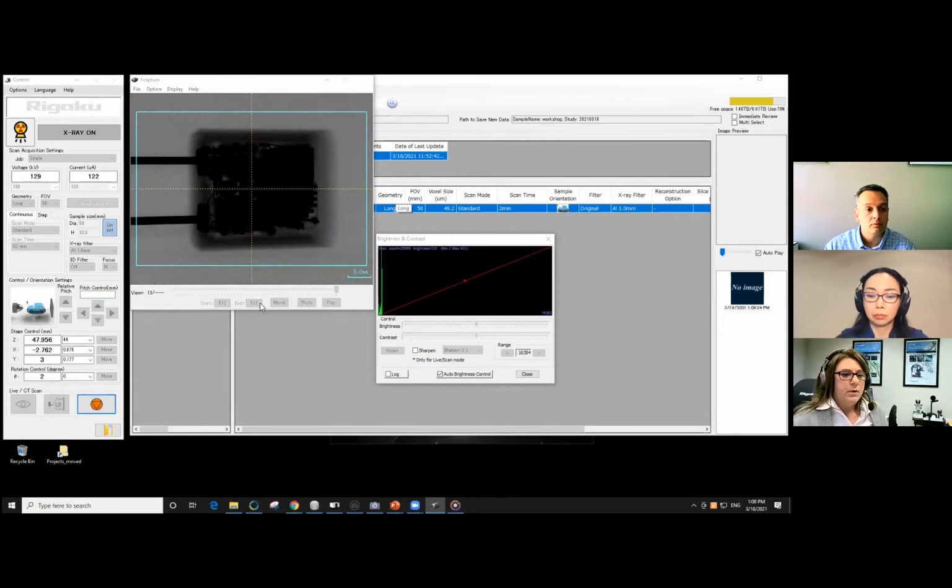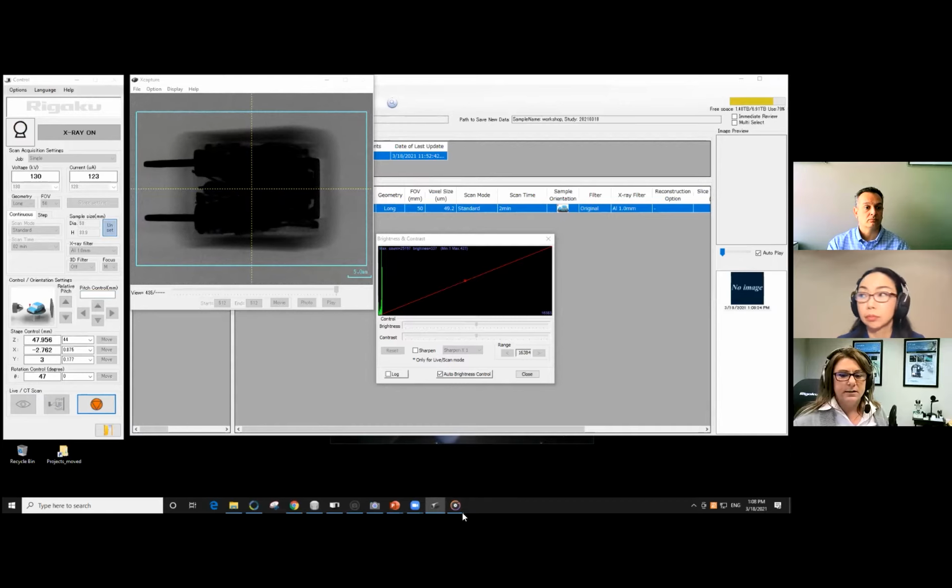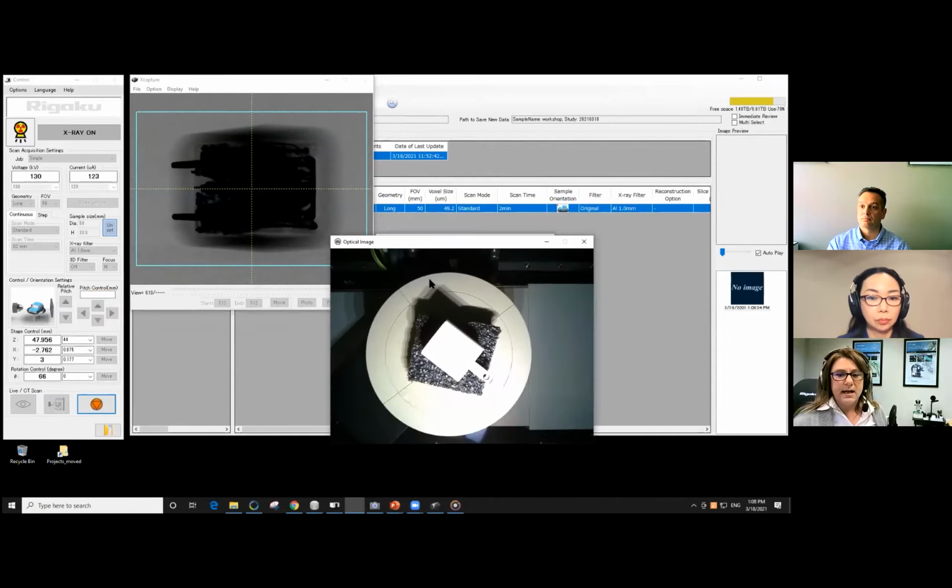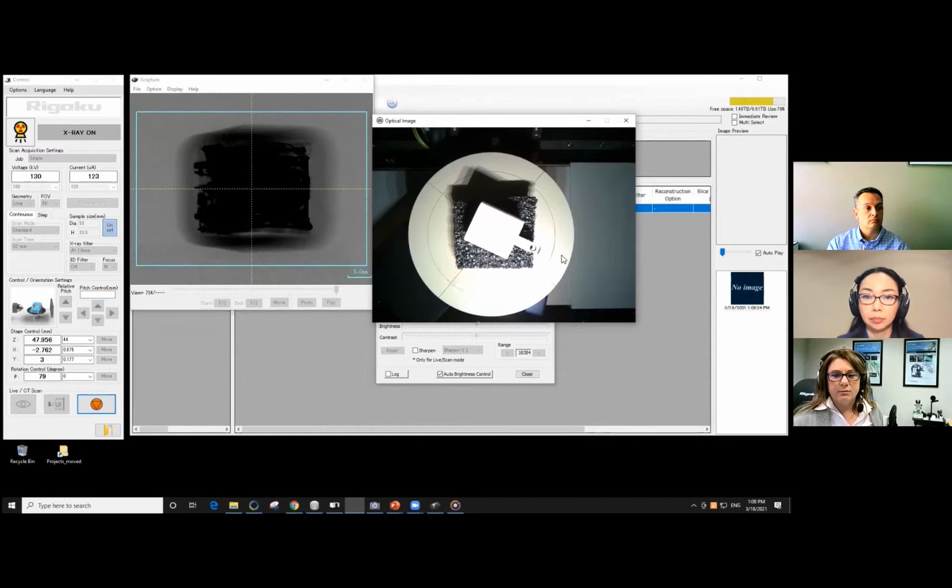Okay, so we can track the progress of this measurement by looking at the rotational control in degrees. It's going to rotate from 0 to 360 degrees, now at 29, 30, and increasing. We can also watch this field. So it's basically 2D radiographs that are collected along those degrees. And then finally, we can have a look inside the instrument, and you can see the Apple plug here that's rotating.